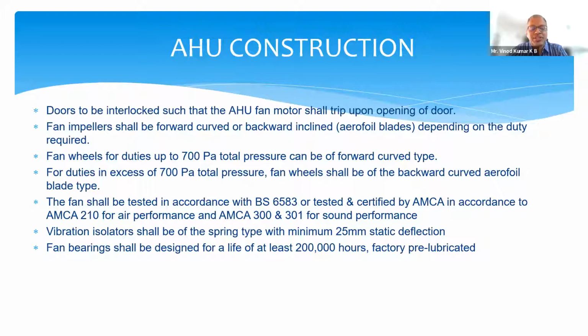But what happens is the technician, under pressure to handle the problem, forgets to switch off the main switch or the isolator, and he will just go and open the AHU without knowing that the AHU is running or that the isolator has not been switched off. This is going to be a serious risk factor for the technician. So it's mandatory to interlock the AHU door with the motor.